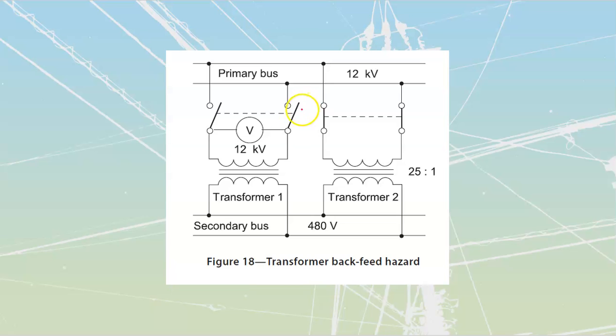Normally, if this switch was closed, I would have these two transformers operating in parallel, both supplying power out to this secondary bus. We'd be taking power in on the primary bus and supplying it out to the secondary bus. Let's say that for whatever reason, we have to work on this transformer.